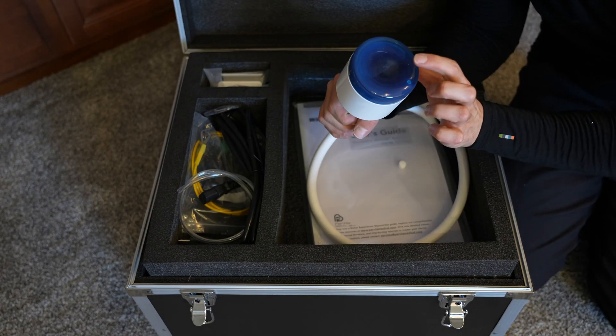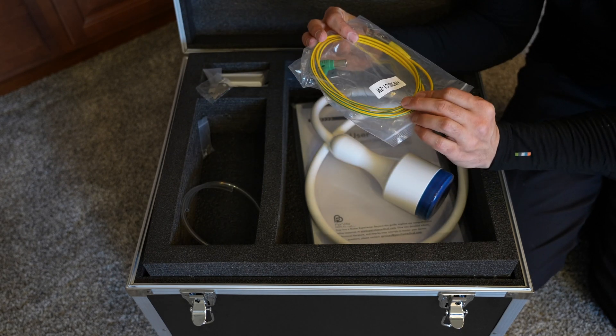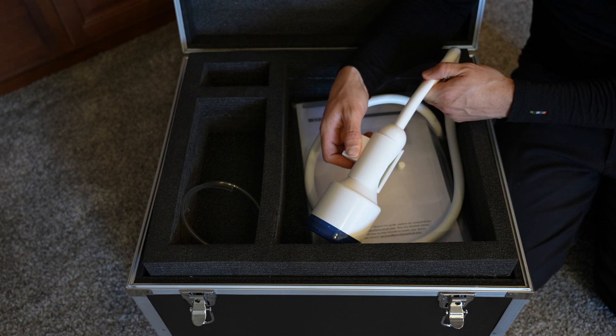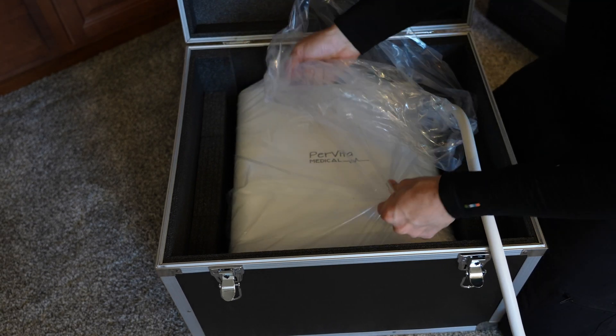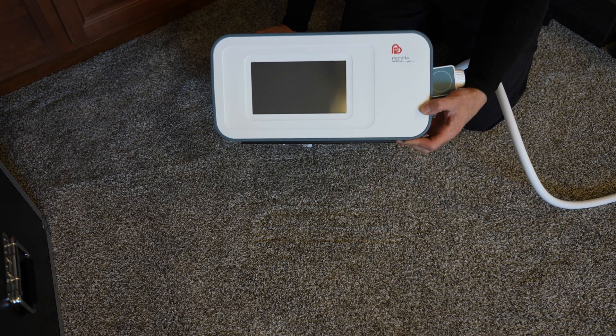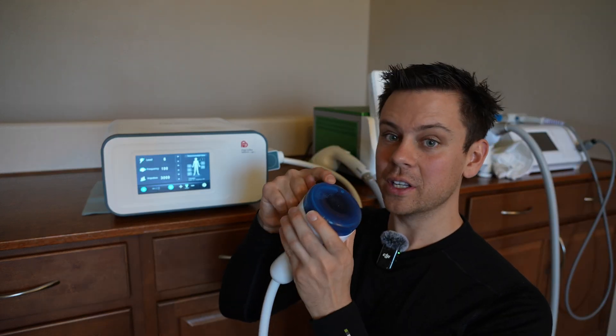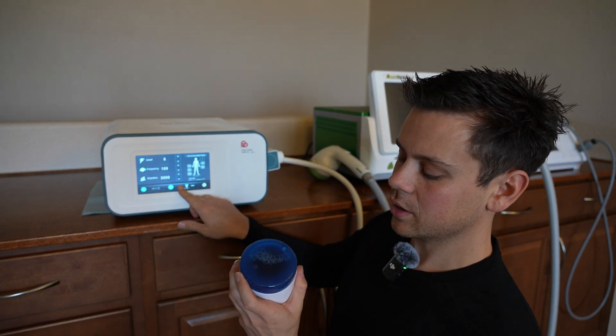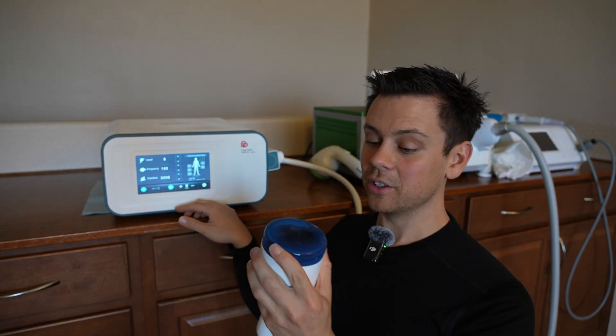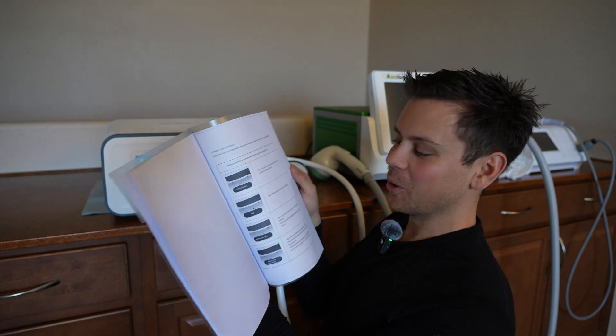Let's open it up. The applicator has water inside already — that's different. We have a main power cord and a grounding conductor. Before starting, there are bubbles in the head that we do not want. Fill it with distilled water — do not use tap water. There's a water hose attachment at the bottom of the machine. Remove the plug, stick it into a cup full of distilled water, go to settings and press plus, and it will fill itself up with water by sucking it out of the cup.